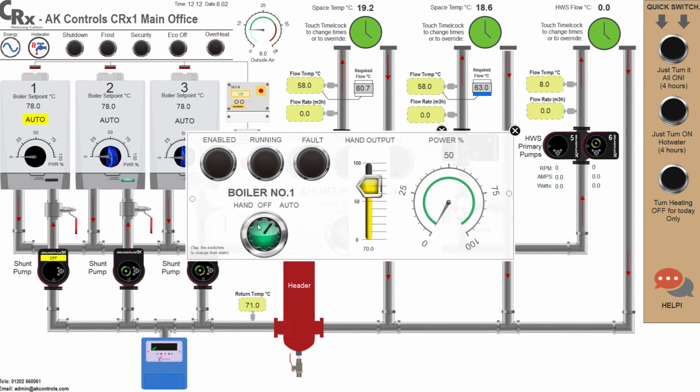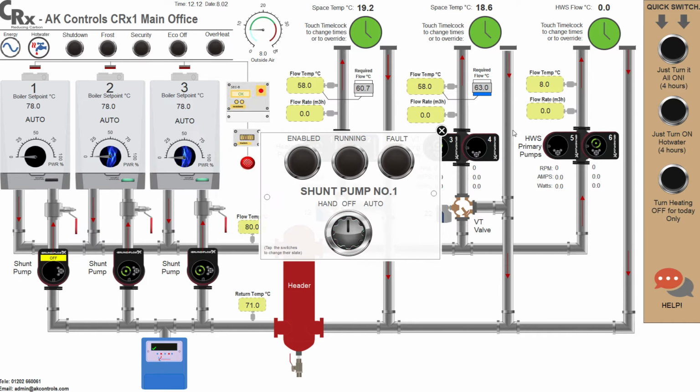Again, if the switch is left in the off or hand position for more than an adjustable period of 1 to 5 days, an alert email is sent to the designated recipients.